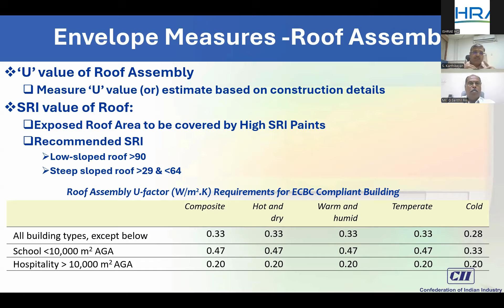The ECBC codes guide us in terms of the U value we can choose, depending on the climatic conditions we are in, whether composite or hot and dry or warm and humid. According to the U value, we decide on the construction of the roof or wall. In case of a wall also, the U values have been mentioned, and these values will vary with respect to the typology of the building. If it is a high energy intensive building, we need to be more stringent in deciding the U value.